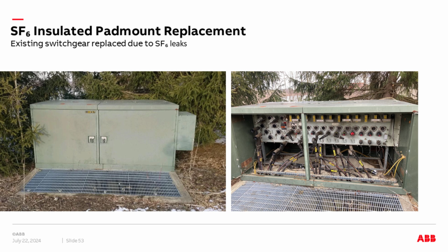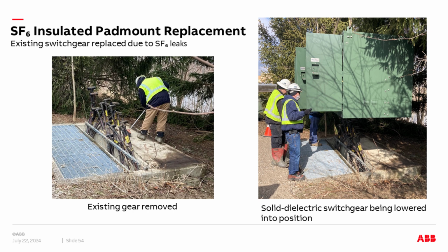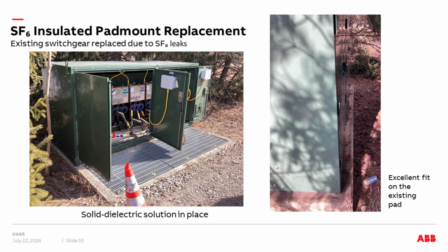Anyway, this is a piece of SF6 gear that the customer wanted to replace. And again, you can see, I don't know if you can see it, but there's a pit that the cables come out of. So there's a bit of room to move things around, which makes it a little easier. There's a better picture showing the pit after the gear's been removed. This is a low-profile, single-sided piece of gear that the customer was very concerned about replacing in the same footprint to avoid putting something in that was bigger or more obtrusive, or where they had to do a lot of rework on the pad and the cables.